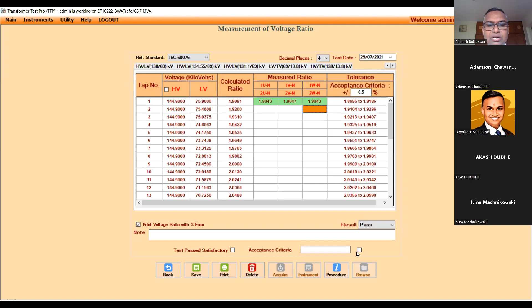Now you have a facility here to print voltage ratio with percentage error. You can also put in your notes. You can also give a comment whether it is a result you want to show as pass, fail, whatever it is. You can set your acceptance criteria which will appear in the test report, or you just want to pass a comment, test passed satisfactorily. That is also possible to be chosen from here.